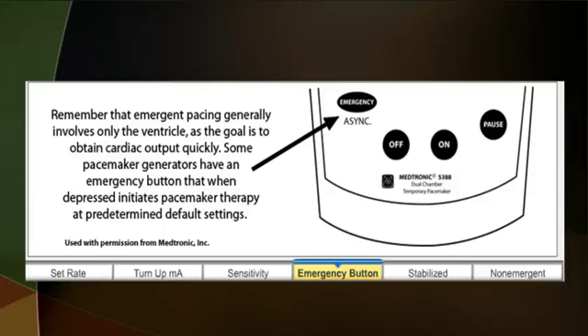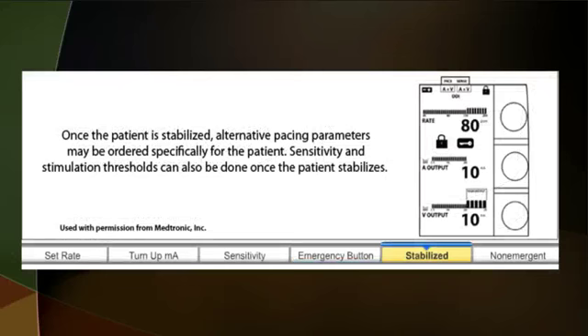So our pacemaker generator, Medtronic product, actually does have this emergency button. It's bright red, and when it's depressed, it will put the pacemaker on at a predetermined default setting. And it does, if you remember, asynchronous pacing. So if you remember earlier what we talked about, demand mode is much more preferred. Once your patient is stable, alternative pacing parameters may be ordered specifically for the patient. Sensitivity and stimulation thresholds can also be done once the patient stabilizes, but should not be done until then.